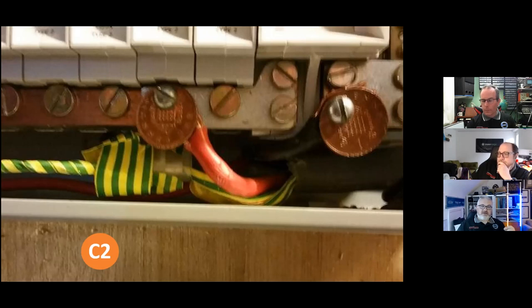But the fact of the matter is, if you go purist on it, just on that photo, there's no signs of thermal damage. If I check it for tightness and it's tight, it's completely wrong in every way, shape or form. It's a C2 or a danger notification. It might be that it feeds a bit of equipment that's not actually used a lot or isn't used. So there are some things you can do to engineer your judgment. Yes, it's the perception of risk, isn't it? That's the fun of this, I guess.